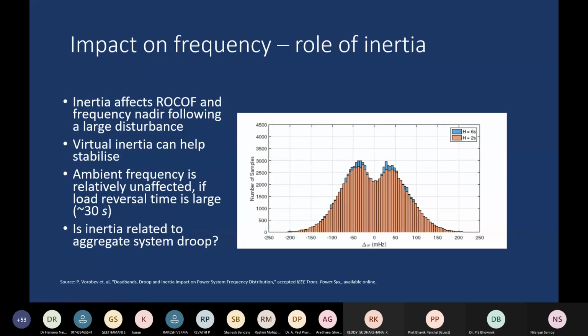Now, there is another kind of frequency study that we at IIT Delhi are also doing. There is a recent paper available in IEEE Transactions on Power Systems from a group from MIT, which talks about ambient frequency. How is the ambient frequency affected because of the inertia? Here we have observed that the role of inertia is relatively unaffected. It does not affect the ambient frequency. It only affects the frequency distribution when there's a big load change.